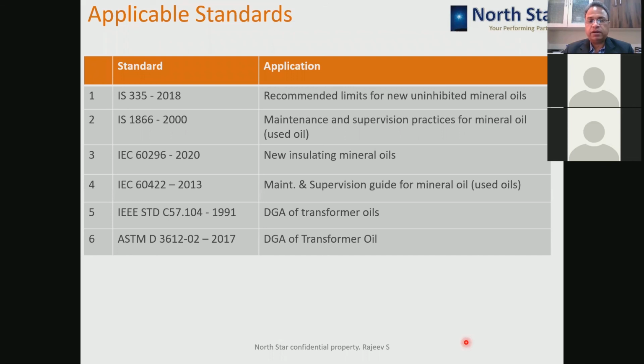So what I mean to say is, all these standards are for mineral oil. They are not for synthetic or natural esters. For example, the DGA of natural and synthetic ester could be a little bit different than for mineral oil, because all these references, even for dielectric tests like tan delta, are based on the compilation of data of transformers which were already manufactured. So those transformers were made with mineral oil and paper-based insulation. The same kind of data will not be applicable for other insulation systems like synthetic ester or natural ester and solid insulation combination.